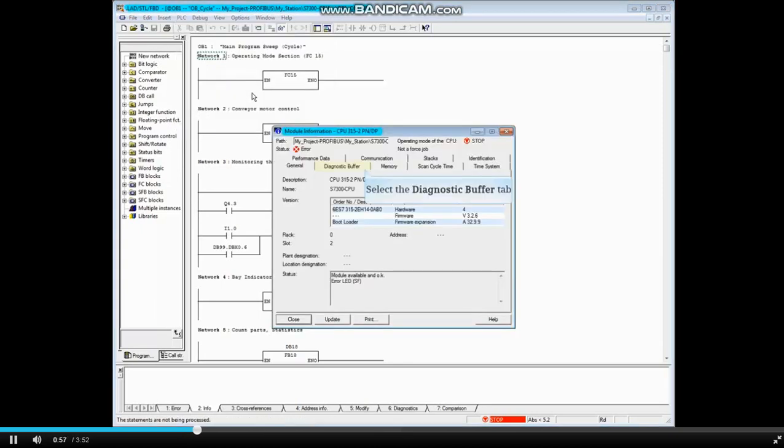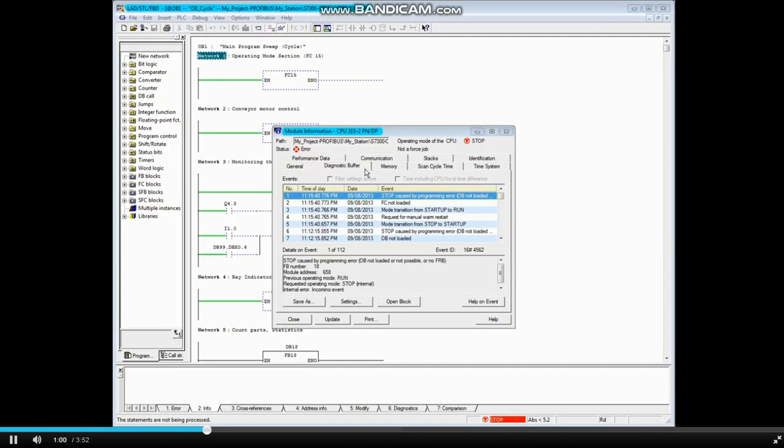Click on the Diagnostic Buffer tab. Message 1 shows that the CPU has gone to the Stop mode. In the Details window, you can see that the fault occurred in Function Block 18.